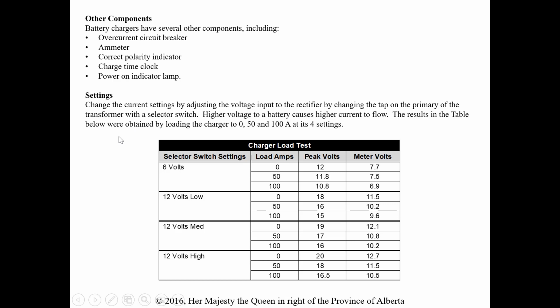Settings: to change the current setting, you adjust the voltage input to the rectifier by changing the taps on the primary of the transformer with the selector switch. So here are our different taps, 6 volts and then 12, low, medium, and high. Okay. Higher voltage to a battery causes higher current flow. So when we were looking at this test, it was basically with load amps of 0, 50, and 100. Okay, for every selection it did that. So it went from no load, half load, full load for each one. Then it showed the peak volts for all those, and then the current, and then the meter volts.